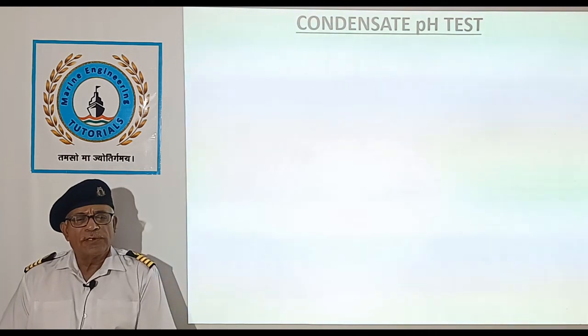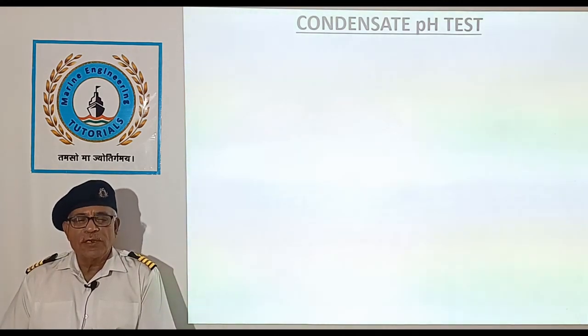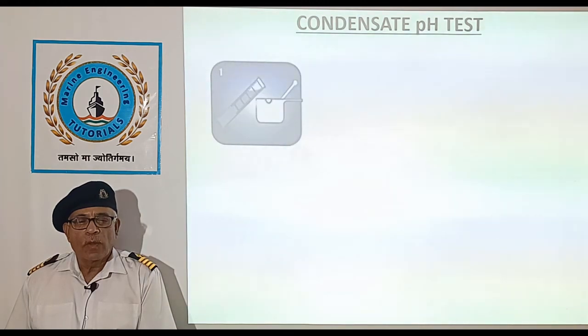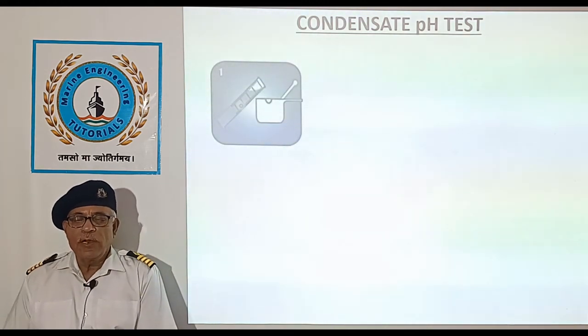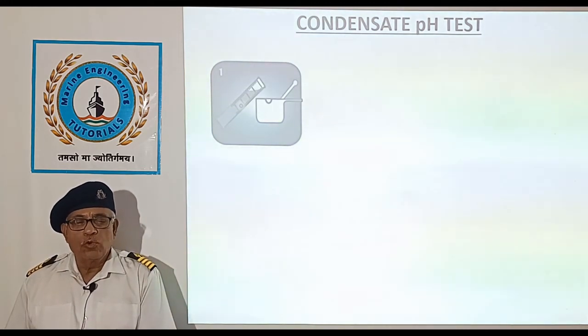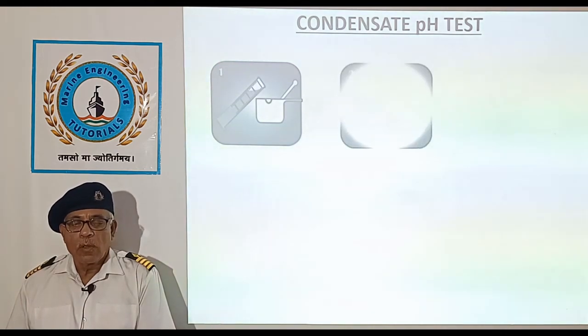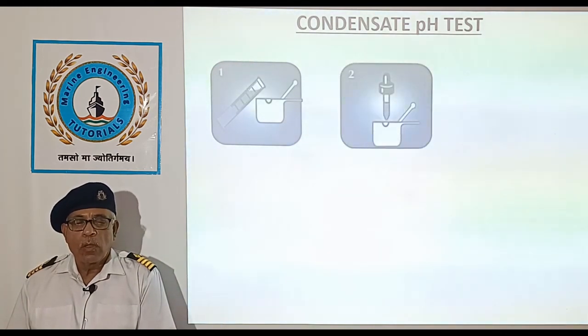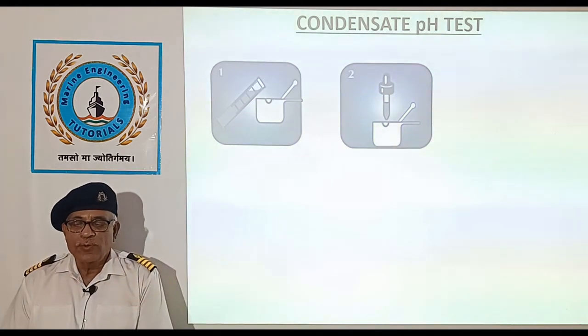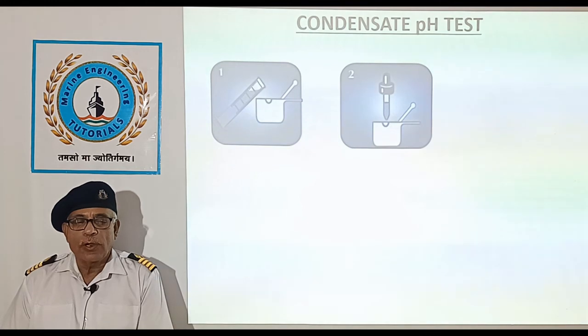The last test is the Condensate pH Test. The following procedure is used to carry out the condensate pH test. Collect 50 millilitres of cold condensate sample and pour into an evaporating dish. Add 3 drops of phenolphthalein indicator — the sample should turn pink.